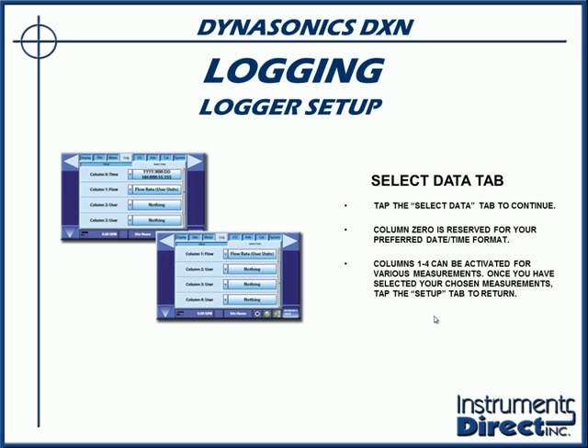In this case, column 0 is reserved for your preferred date time format. So you can select the format that you want to use to log your data. And then columns 1 through 4, you can select the specific type of data that you want to look at. So if you want to look at flow rate, totalization, signal strength, temperature, and so on, you have all the choices. Whatever's in the machine, you can select up to 4 different points to do that.